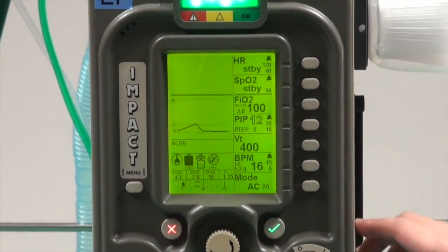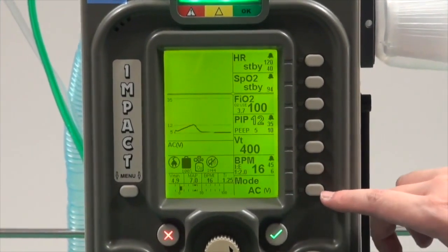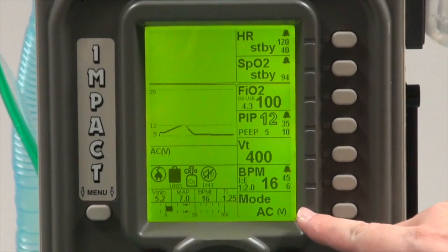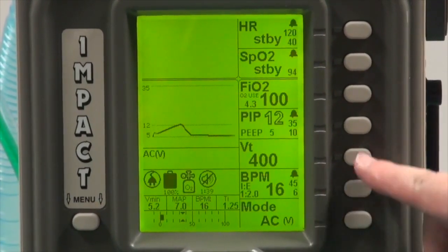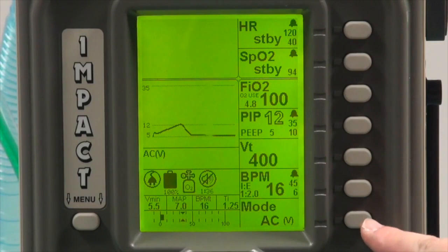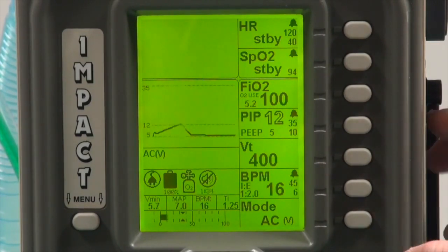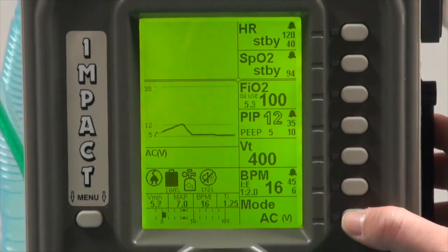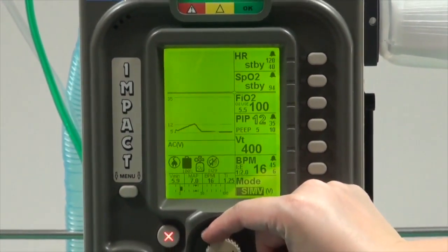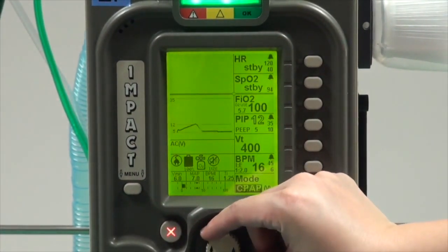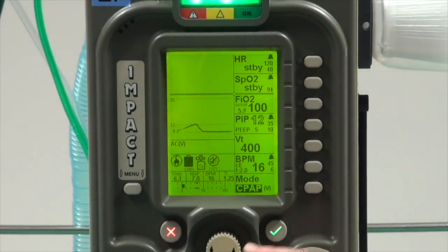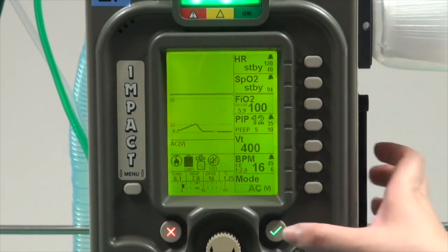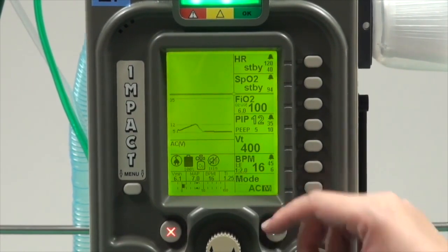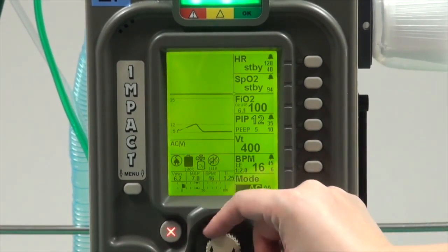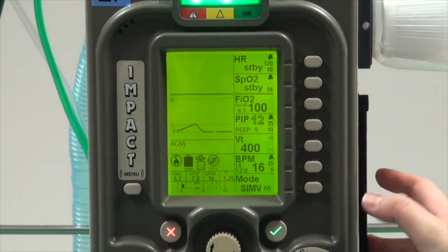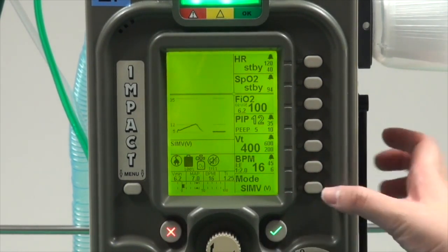If you look at your ventilator, starting from the bottom, this button corresponds to this rectangle. Similarly for all the rectangles and buttons above it. Starting with the mode, in order to change your mode between AC, SIMV, or CPAP, I just need to turn the wheel and confirm with the tick. Notice how it's changed to SIMV mode.